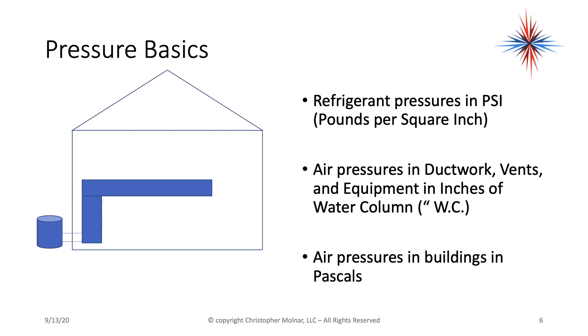Refrigerant pressures are measured in psi — pounds per square inch. Air pressures in ductwork, vents, and equipment are measured in inches of water column. Air pressures in buildings are measured in pascals. To summarize: refrigerant — pounds per square inch; ductwork, vents, and equipment — inches of water column; buildings — pascals.